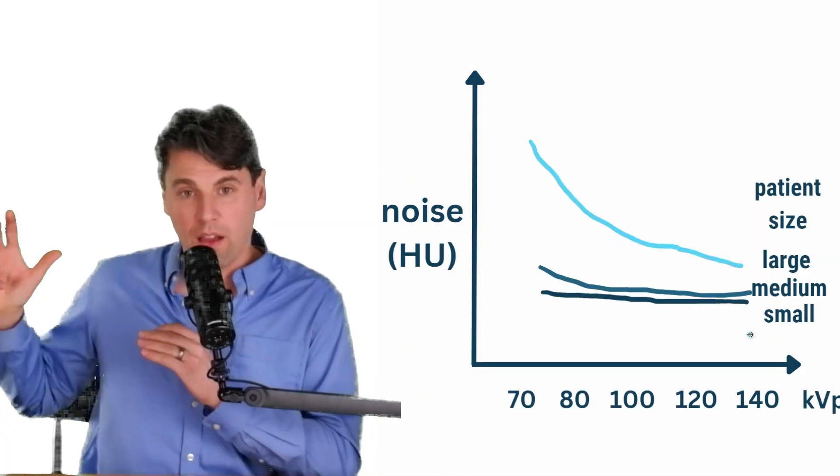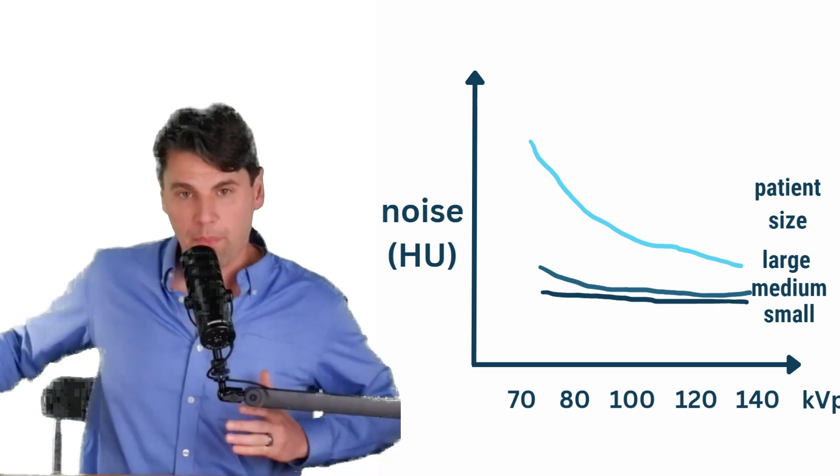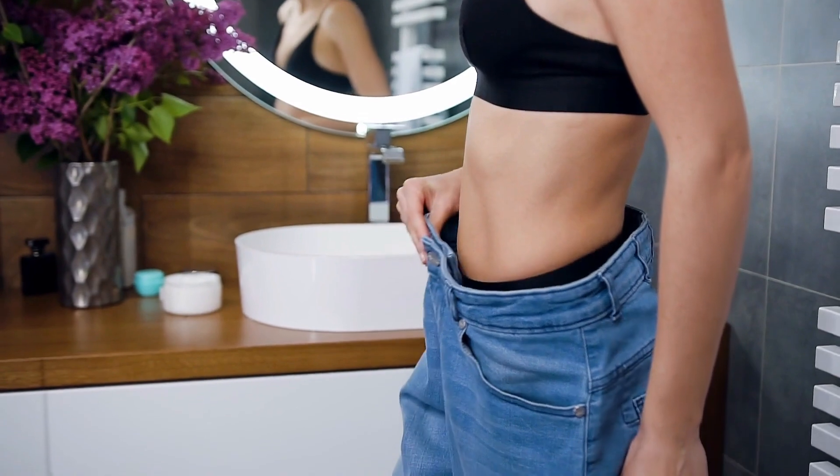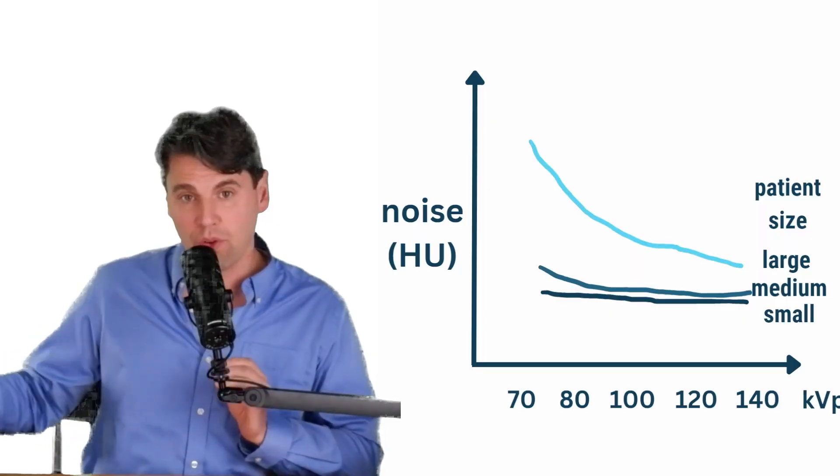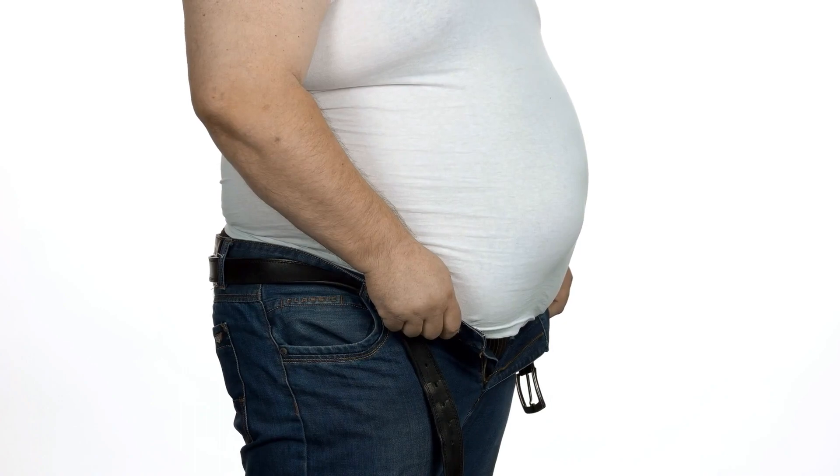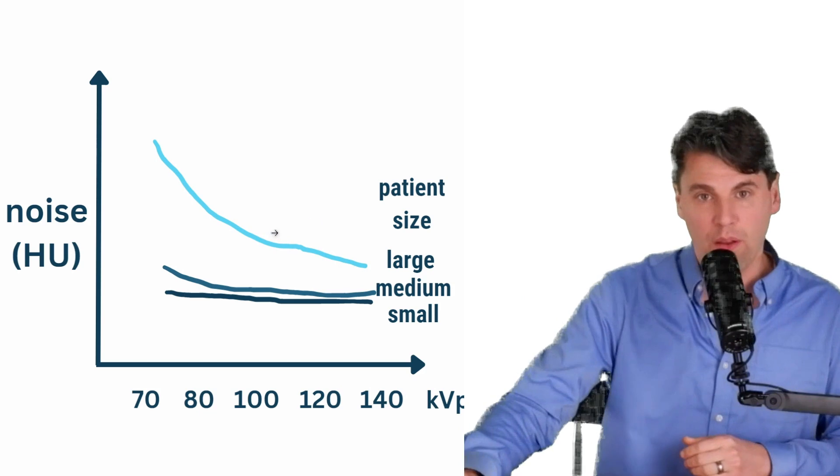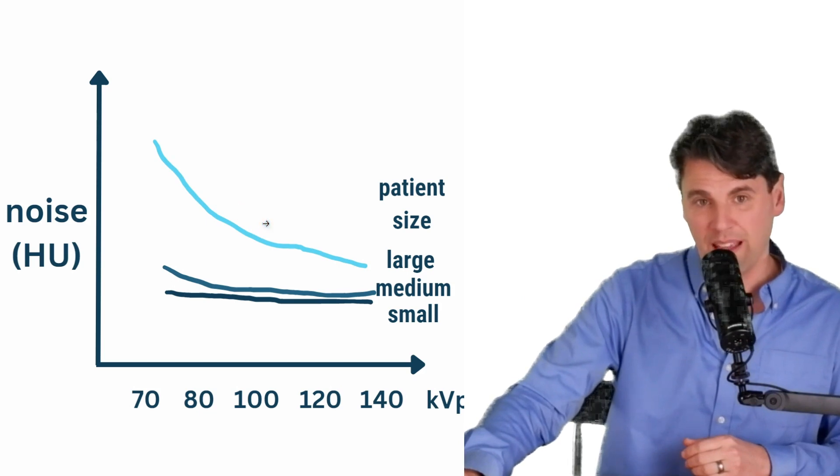We've also talked about the penetration of the beam being an important quality. So depending on how large your object is, for a relatively small object, you're actually going to be relatively stable in terms of the noise in your image. If you go to lower KVPs and give the same dose, if you have large objects, you're actually going to see a really steep increase where you get to that point where you're getting relatively fewer photons through the patient. And thus this is leading to a very noisy image.